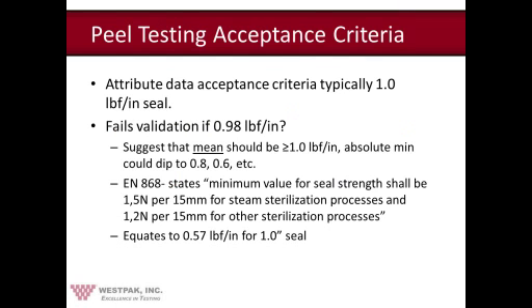So another snag that we see many medical device customers run into is the inflexibility within peel testing. Now this testing, often referred to as attribute testing, measures the strength of a seal, typically Tyvek and poly pouches, when they're pulled apart. Kevin talked about this earlier.